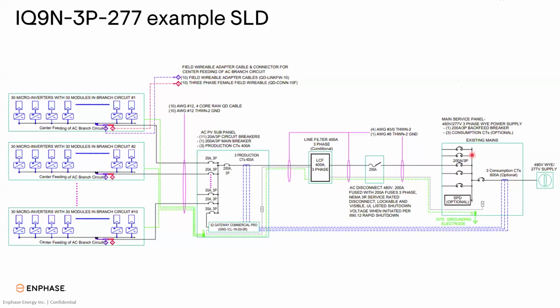Moving over to our typical connection, that's really site specific, as are the number and size of disconnects. We have our consumption CTs, which are optional, and those get wired back to our gateway. Those are rated for 600 amps. So if you have a service entrance larger than 600 amps and you need consumption monitoring, because one, you want to monitor consumption, and two, you want to be able to limit the site's export, not an issue. We have a third-party metering system that will allow for up to 1200 amp CTs, and that easily integrates with our gateway.